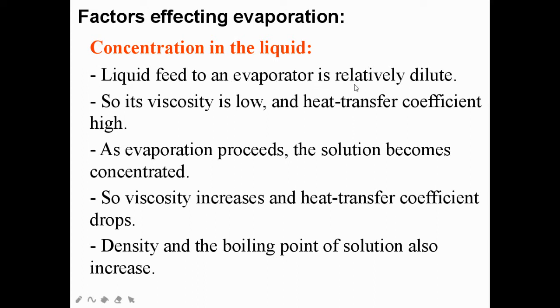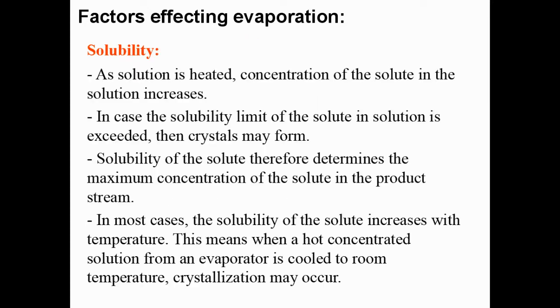Liquid feed to an evaporator is relatively dilute, so viscosity is low and heat transfer coefficient is high. As evaporation proceeds, the solution becomes more concentrated, so viscosity increases and heat transfer coefficient drops. Density and the boiling point of the solution also increase.